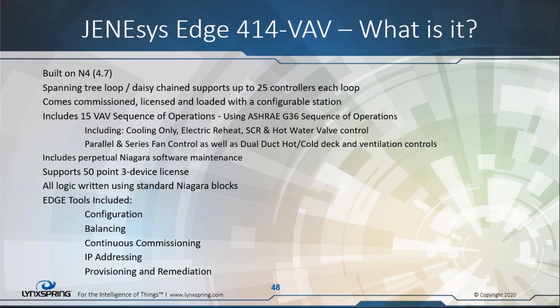I'm going to move a bit more quickly here. The tool set enables a user to quickly configure every unit on a bus, so you're not individually touching and configuring every VAV controller. The tool we give you will go out there, find the individual devices, and configure them the way they need to be—so you may have five cooling-only units, five units with electric reheat, and some others.